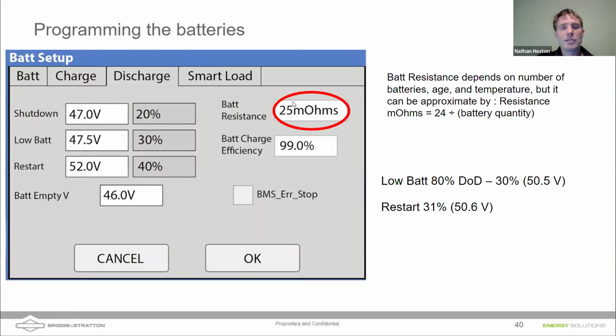If your battery bank is shutting down a little bit too early under load, it has to do with the battery's internal resistance, which is why you might get to the voltage where you've set shutdown to occur, but it's not going to do that because it's under a heavy load, and so the actual resting voltages of the batteries are higher. So you do want to pay attention to this and input this. If you're continuously in cold environments, you might consider increasing this number a bit in the winter months and decreasing it in the summer months if the temperature of your battery bank varies. 99% efficiency we keep here.